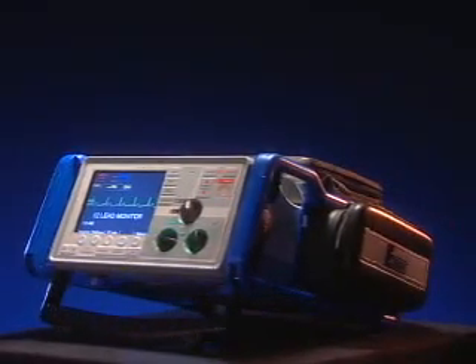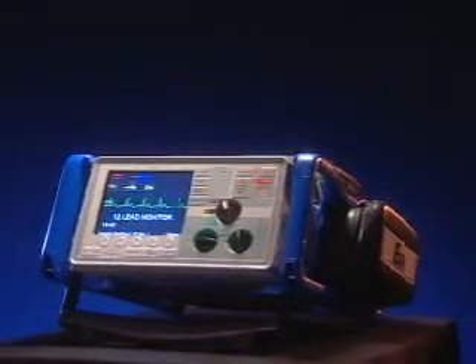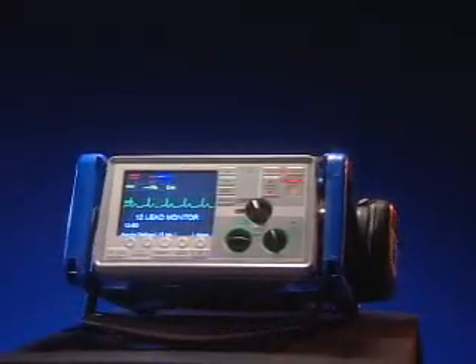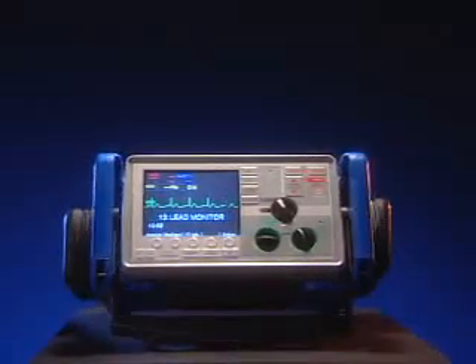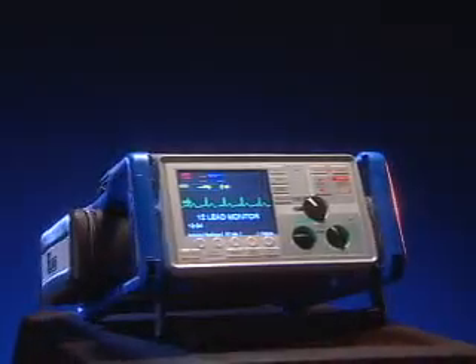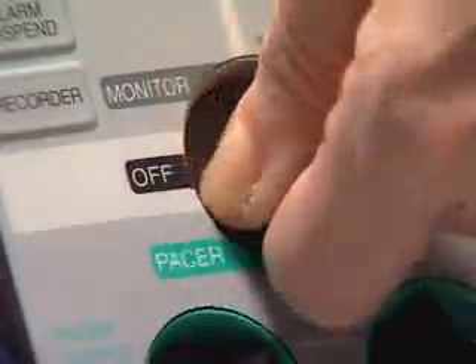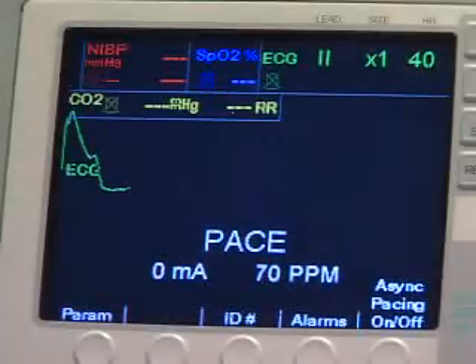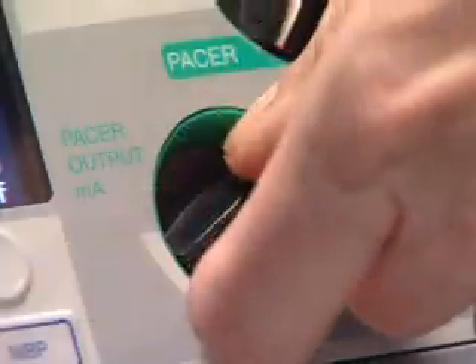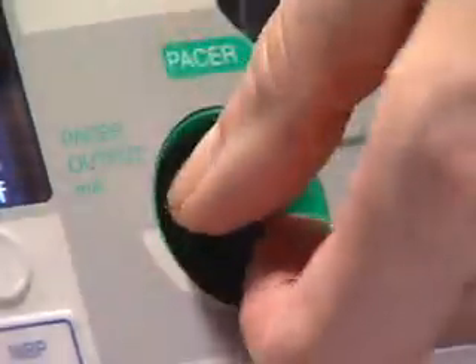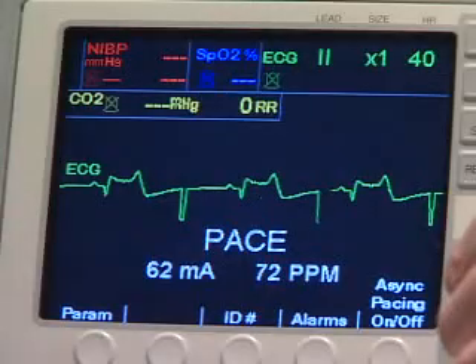E-Series defibrillators use a demand pacemaker option. To use the pacing option, apply ECG electrodes and the multifunction electrode pads to the patient and turn the selector switch to Pacer. Set the pacer rate to a value that is approximately 10 to 20 pulses per minute higher than the patient's intrinsic rate.